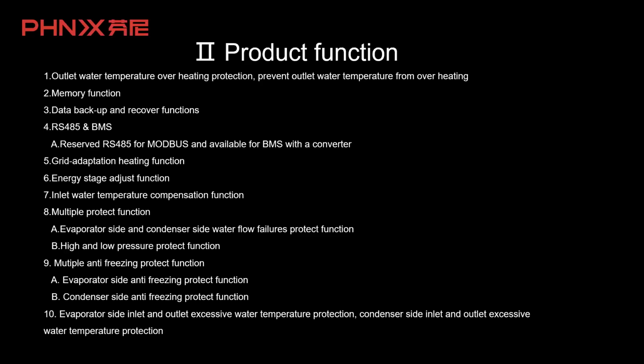So what's the energy stage adjust function for the HeatMax water source heat pump unit? Could you explain to our customers? I think this will be difficult for me. So there will be 0% with no compressor on. 1 compressor on means 25%. 2 compressors on, 50%. 3 compressors on, 75%. And 4 compressors on, 100%. That's the energy stage adjust function. Have you got it? Yes, thank you. So let's move on.